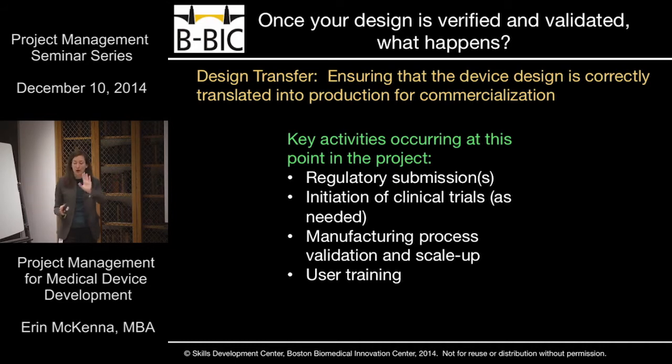You can continue work on that while your regulatory submission is undergoing approval, because the main thing that they're focused on is understanding the design choices and making sure that they address the user needs in support of the indication that you want. You may, once you have an approval, initiate a clinical trial at this point. You don't have to be in a full manufacturing mode to be building products for clinical work. You could be building products in a batch situation in a lab. As long as they meet your outputs, as long as they meet the specifications, that should be sufficient.